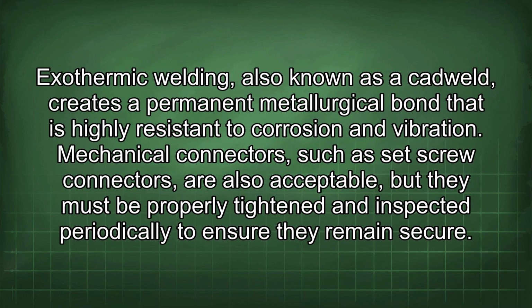Exothermic welding, also known as a cad weld, creates a permanent metallurgical bond that is highly resistant to corrosion and vibration. Mechanical connectors, such as set screw connectors, are also acceptable, but they must be properly tightened and inspected periodically to ensure they remain secure.